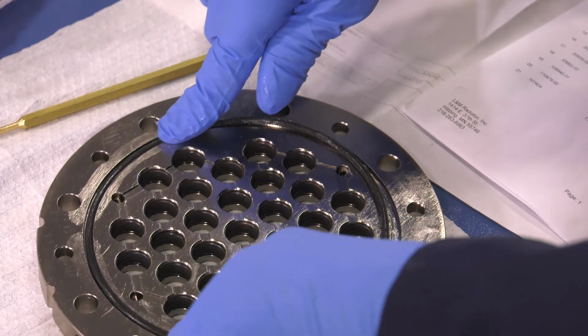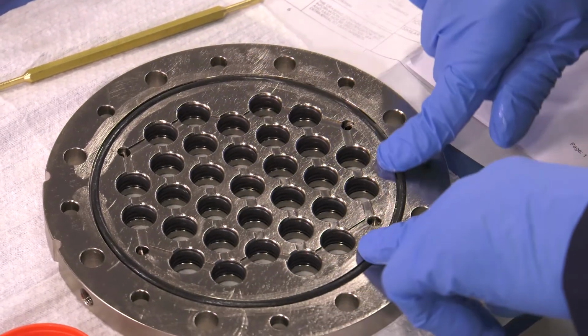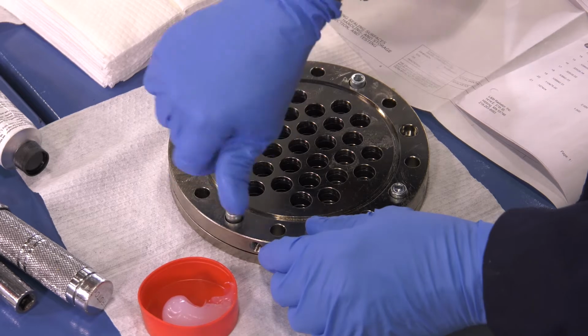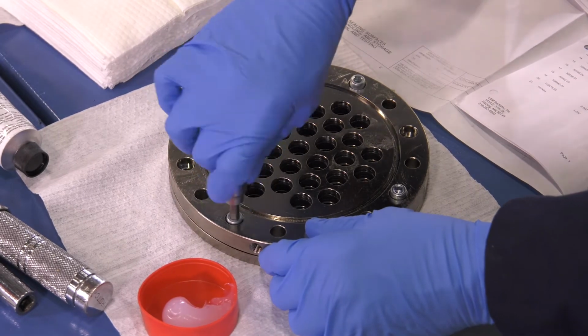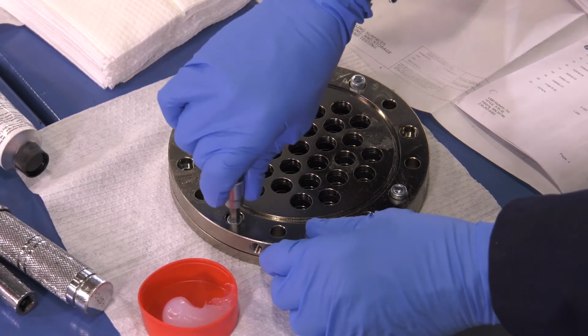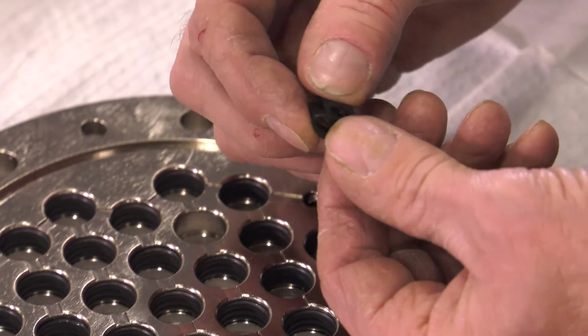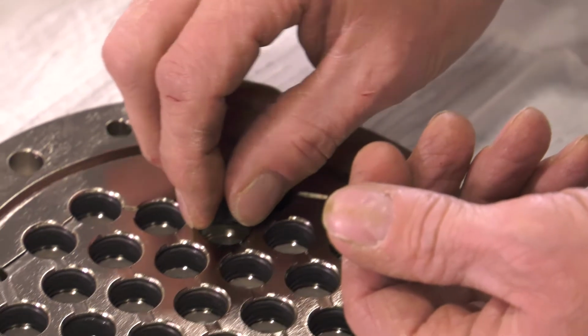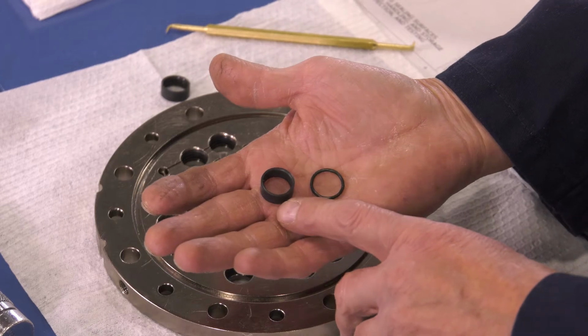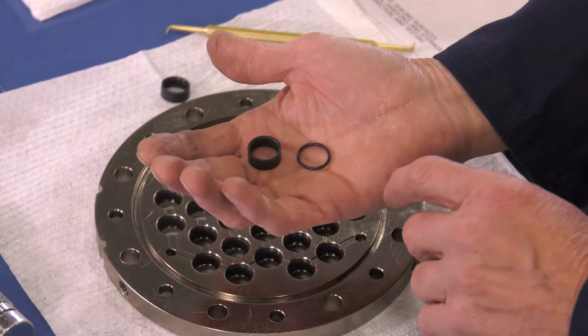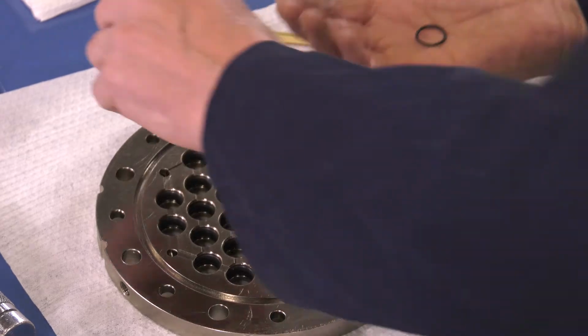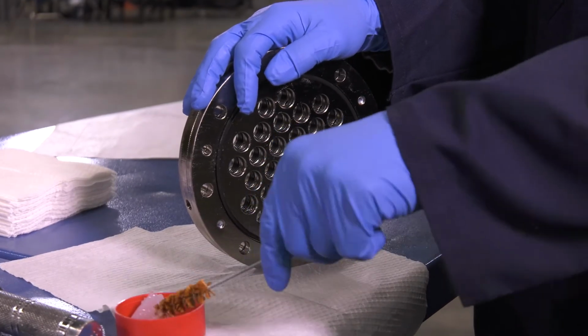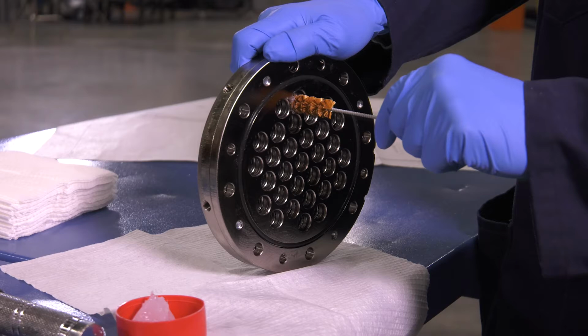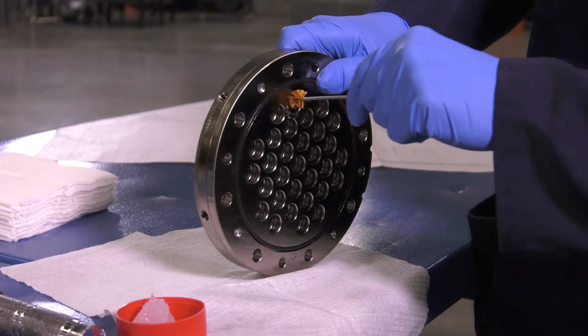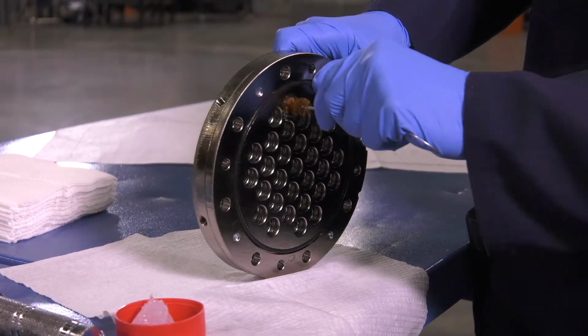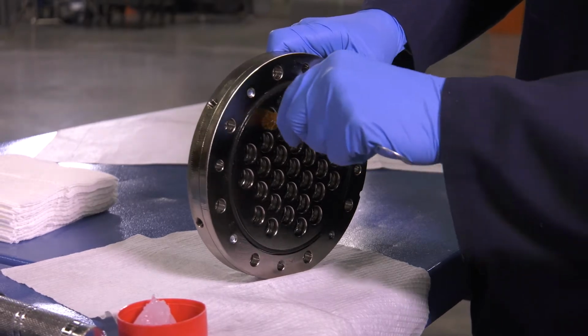Lubricate and install large O-ring seals between header plates. Install the 5/8 inch cap bolts. Do not tighten at this time. Carefully install new seals into the clean headers. Wider seals go into the wider seal grooves and the narrower seals go into the inner seal grooves. Lube the seals with a lubricant and brush specified in the System Protector Service Manual. Adequately lube the seals, but do not use excessive amounts.